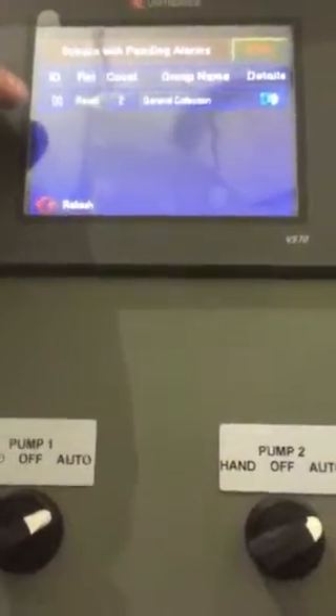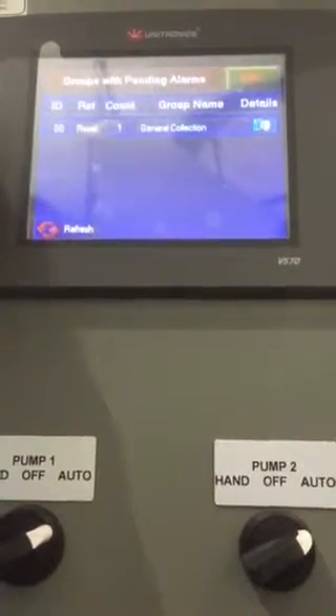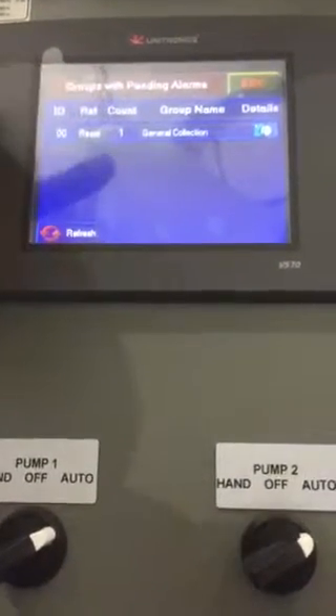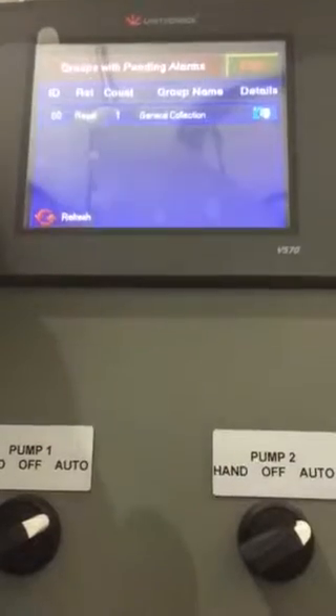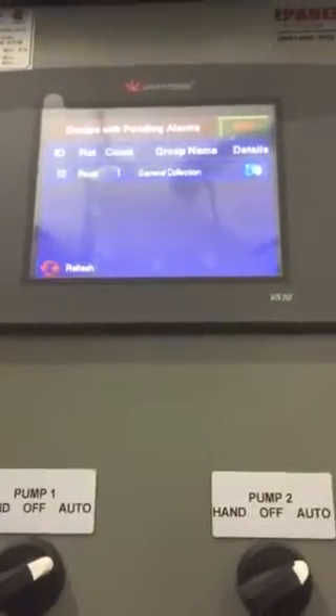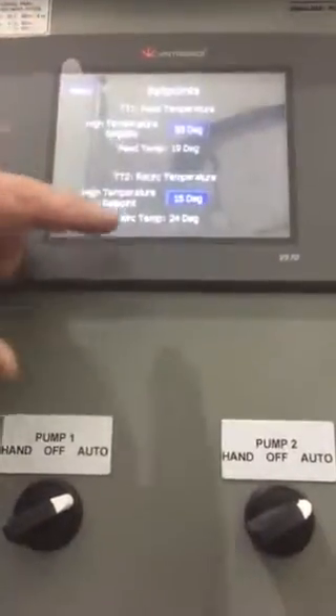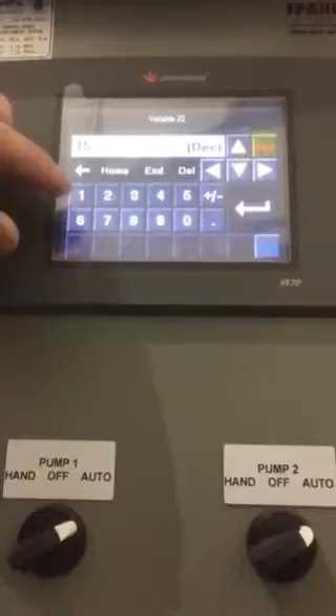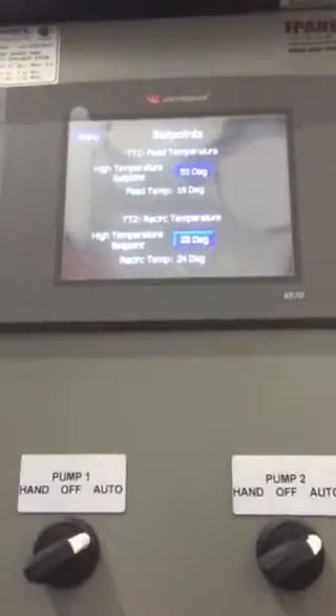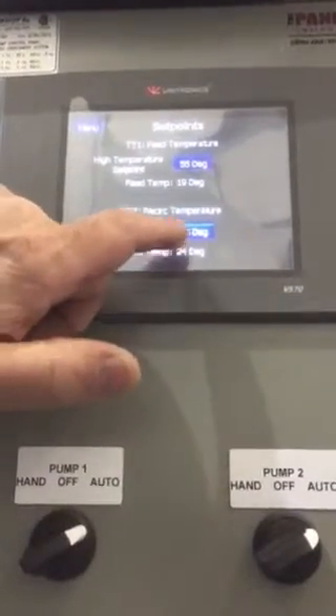Lastly, there's alarms. This basically tells you that we have two alarm situations right now. There's one that's still ongoing, as you can tell. That alarm is because I have the recirc pump running, and I've set the set point below the normal start point so that I can run it, basically. If I set this to a higher number, above the 21 degrees in the room, if I set it at 25, then the pump will stop. It won't restart until the temperature comes up to 25, unless I change it here.